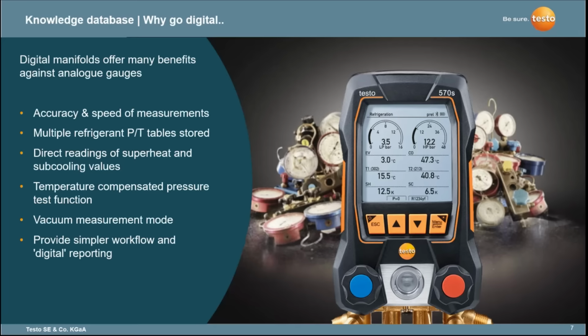You've also got the vacuum measurement mode, so the devices can work in conjunction with a separate sensor to measure vacuum to a very high level of accuracy. And there's compressor discharge line test functions. There's many other test functions within these devices. They're not just a replacement purely for the analog gauge set from a low pressure and high pressure perspective. And also the move to digital provides a much simpler workflow and the digital reporting aspect.